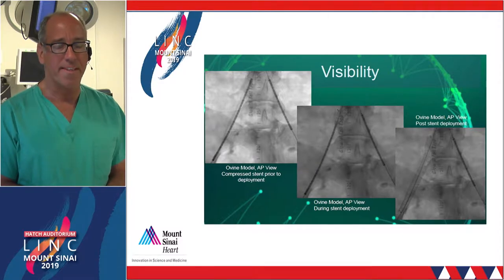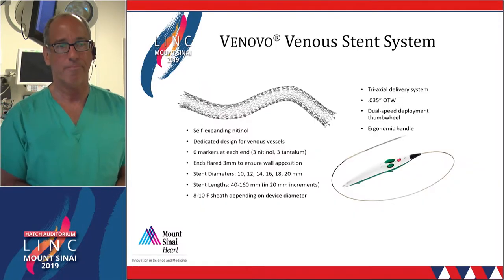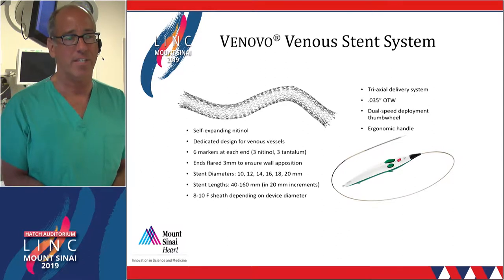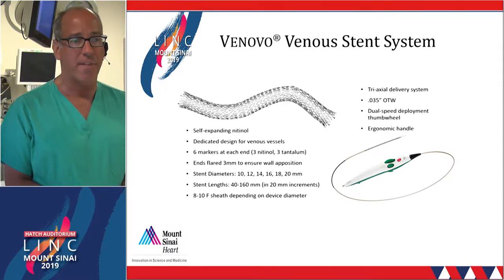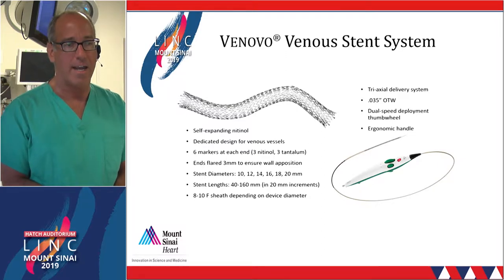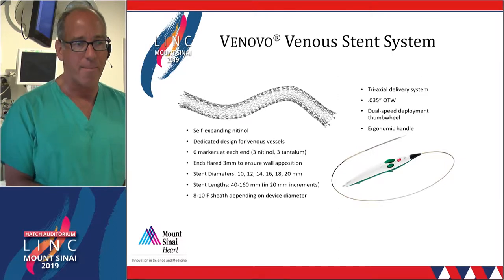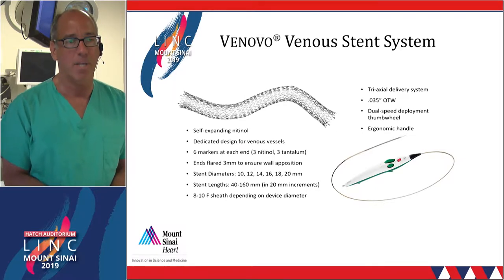The Venovo stent is very visible, which was well demonstrated on the previous case. It is an open-cell, self-expanding nitinol stent. What's unique about this stent is that it has flared ends — the flares are three millimeters in length and make the diameter two millimeters wider than the rated diameter. It comes up to 16 centimeters in length.